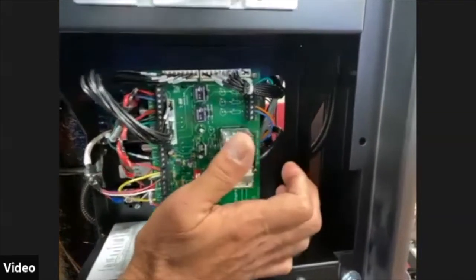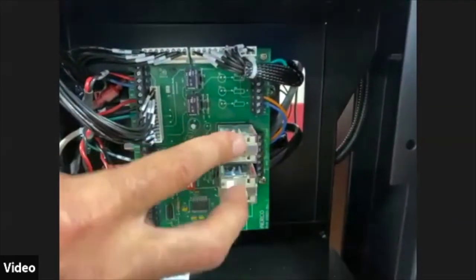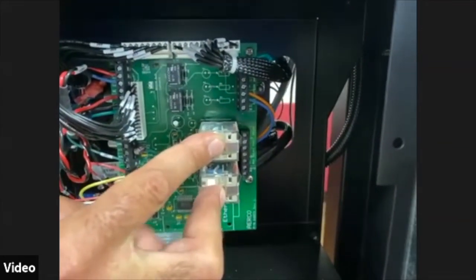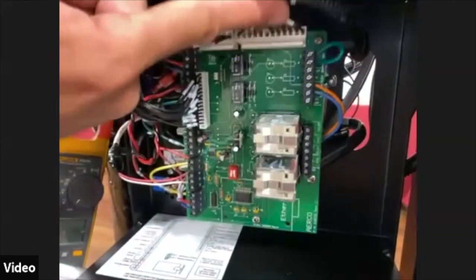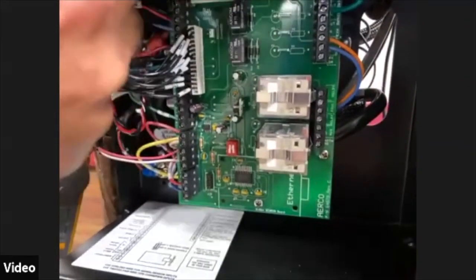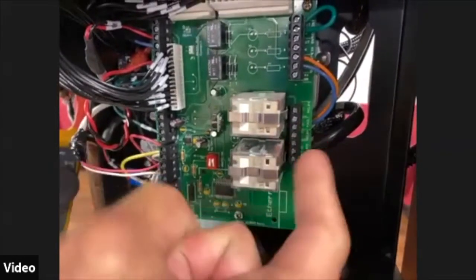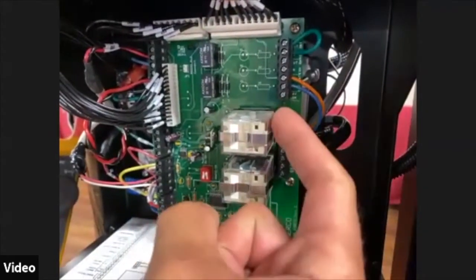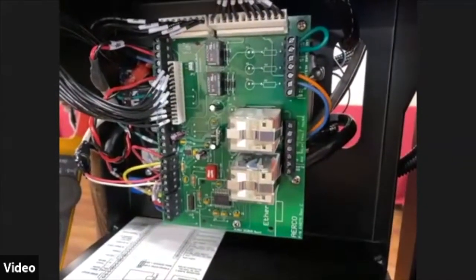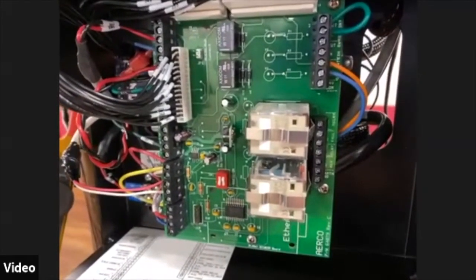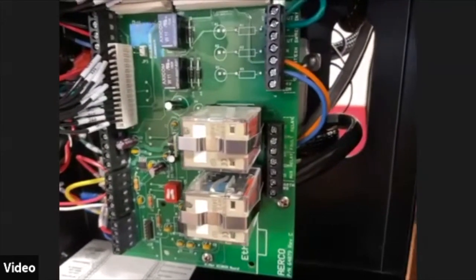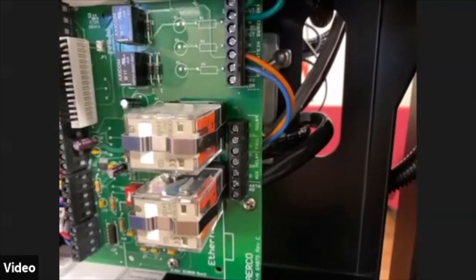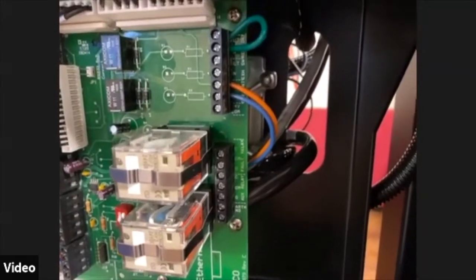We have fault and status relays on here. These are the fault and status relays. I'm trying to keep some of the stuff out of the way and keep my fingers out of the way here, guys. So those fault and status relays are right here. Common, normally open, and normally closed. So that allows the building management to wire them to their likings.